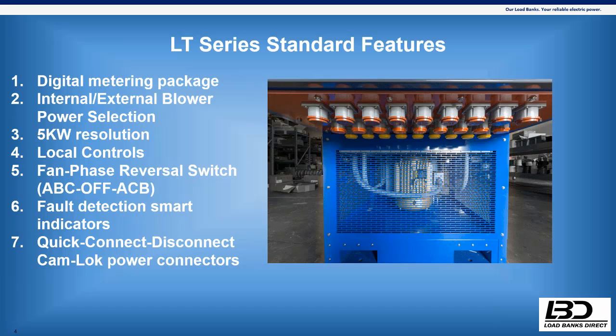Our standard manual controlled units also offer a bunch of safety circuits and fault detection for overloading your motor. Say one of your blowers goes out and you're not getting cooling air through your resistors, the load bank senses that and locks out until it senses air is there again. It also has a safety circuit for over temperature.